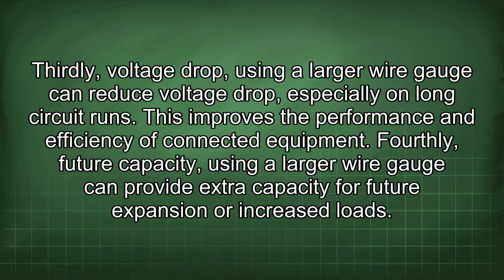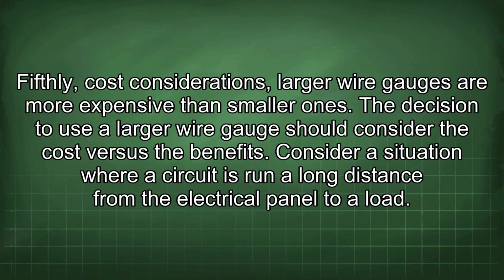Fourthly, future capacity. Using a larger wire gauge can provide extra capacity for future expansion or increased loads. Fifthly, cost considerations. Larger wire gauges are more expensive than smaller ones. The decision to use a larger wire gauge should consider the cost versus the benefits.